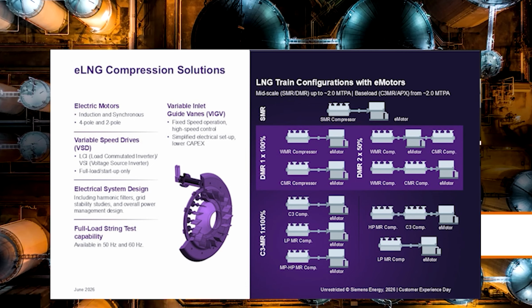In that eLNG space, it's also interesting to note that there's a number of options for process control. So variable speed drives, you'll need them in some way to start these large motors. But there's other ways to do a soft starter without buying a full load VFD. And that might be appealing to some, especially if you wanted to do process control with inlet guide vanes. And that's one thing that we have a lot of experience with at Siemens Energy, with variable inlet guide vanes to control the flow through the compressor.